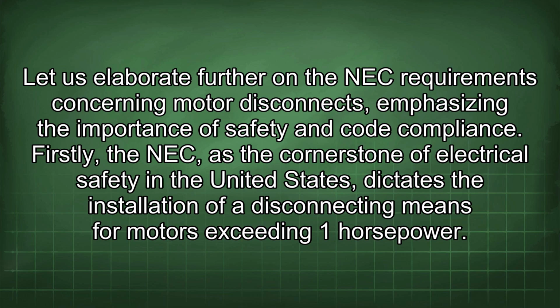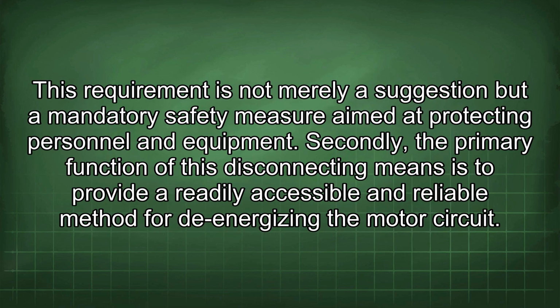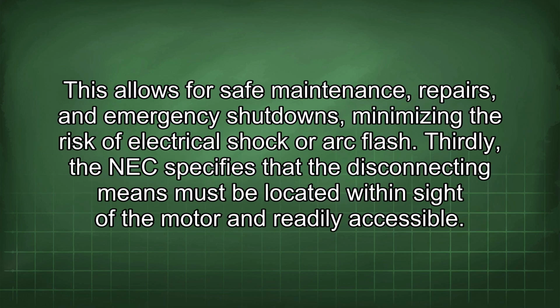Let us elaborate further on the NEC requirements concerning motor disconnects, emphasizing the importance of safety and code compliance. Firstly, the NEC, as the cornerstone of electrical safety in the United States, dictates the installation of a disconnecting means for motors exceeding 1 horsepower. This requirement is not merely a suggestion but a mandatory safety measure aimed at protecting personnel and equipment. Secondly, the primary function of this disconnecting means is to provide a readily accessible and reliable method for de-energizing the motor circuit. This allows for safe maintenance, repairs, and emergency shutdowns, minimizing the risk of electrical shock or arc flash.